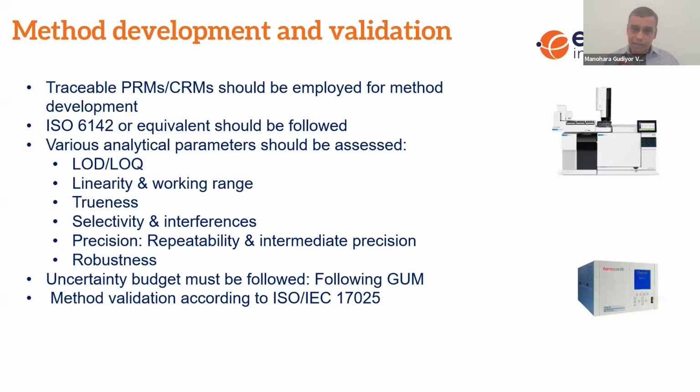Once you do all of this, it's very, very important, probably key to all measurements, to have uncertainty. Without uncertainty, any result cannot be considered, because your results may vary anywhere. As an NMI, we say uncertainty of any measurement is very important. Without uncertainty, we don't accept any measurements. There is the GUM, the Guide to the Expression of Uncertainty in Measurement. It's a very good guide, so I welcome people in this area to go and read it and understand how to develop one.